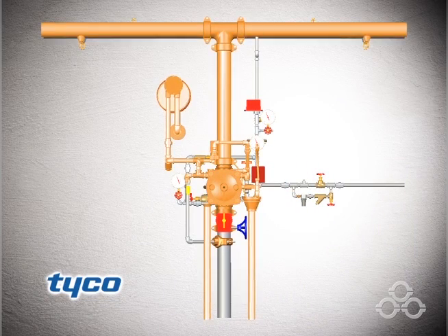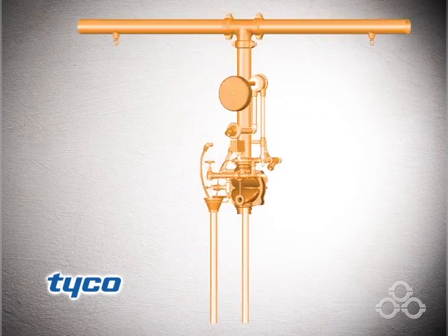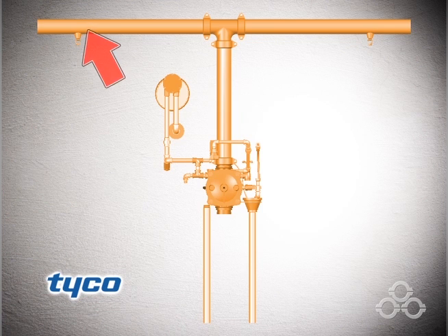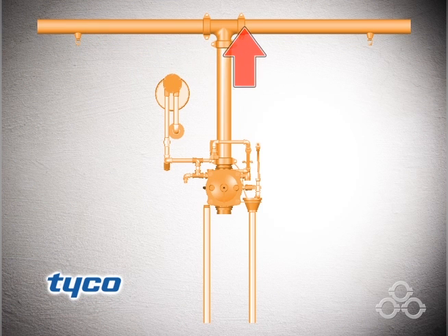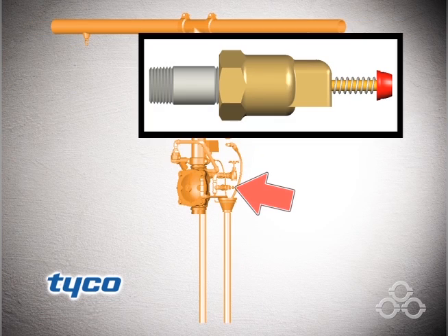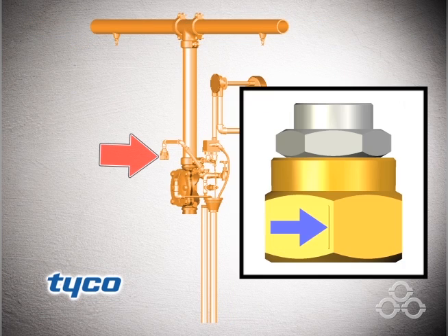The system is open to atmosphere in the location shown here in orange. This includes the system piping with open sprinklers or nozzles, the alarm trim, Model AD-1 automatic drain valve, and the Model ASV-1 automatic shut-off valve pilot chamber.